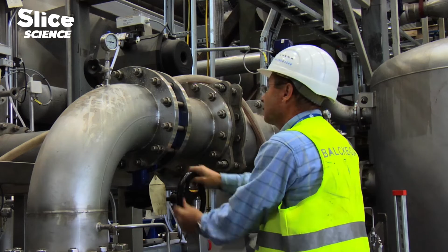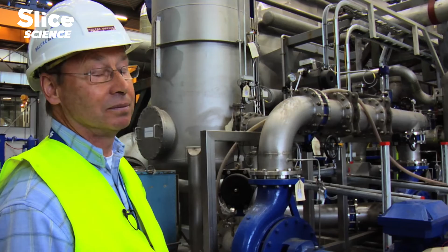We are starting here a cooling circuit, a small circuit with 2 parallel pumps. They are working absolutely parallel and only one pump should work. Now we have tried it on that side. This pump is working correctly and makes a pressure of around 1.5 bars. That should be when the pump is working. And here, this pump makes a pressure of 0. That means no water is flowing, although it is absolutely parallel. And we are assuming that something is wrong here in the suction side.